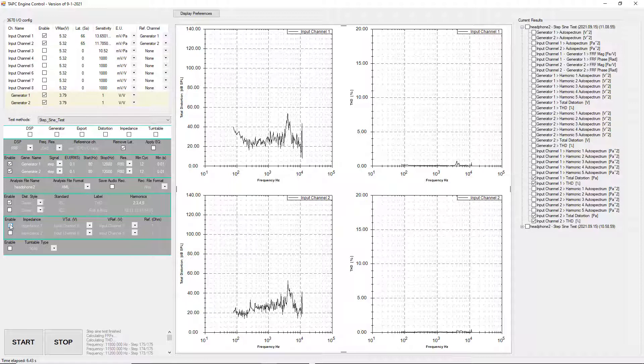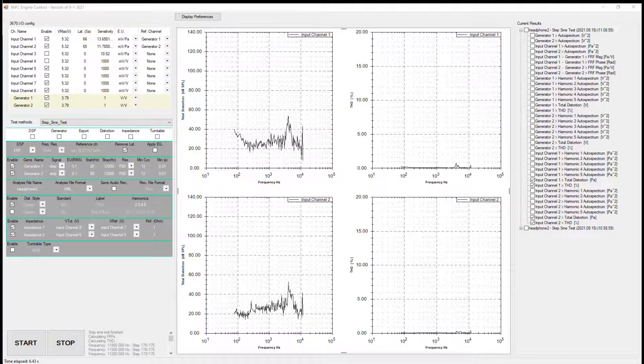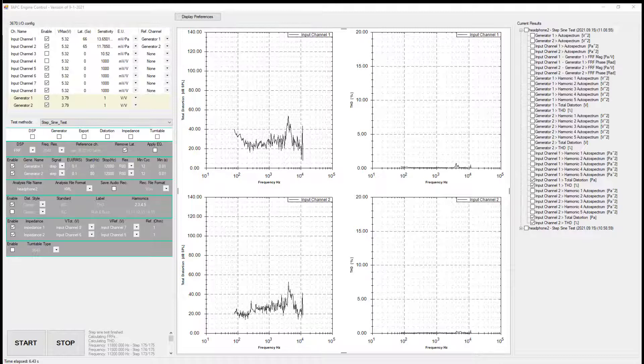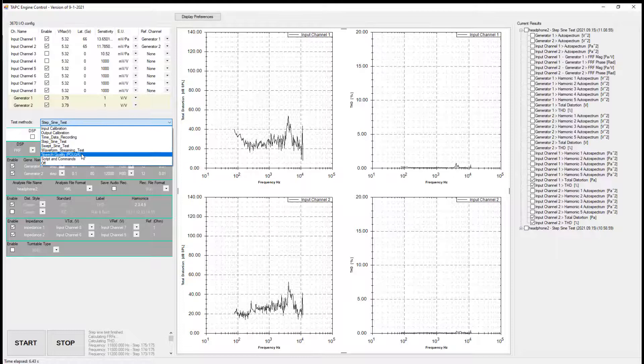This GUI is also capable of calculating electrical impedance by activating the corresponding lines, and can activate a turntable with configurable increment for polar plots. At this point the EA Engine supports multiple test methods: swept sine, random, and waveform streaming for playing back calibrated speech and background noise, with a POLQA metric and additional scripts to come.